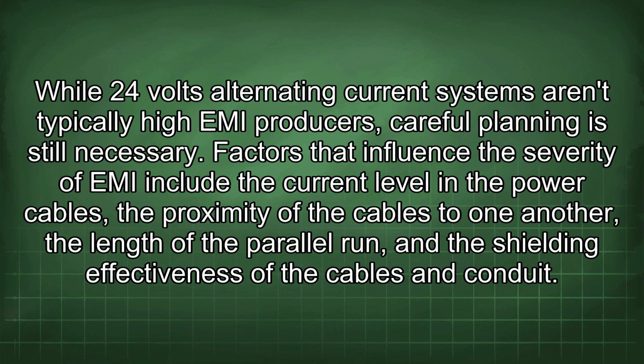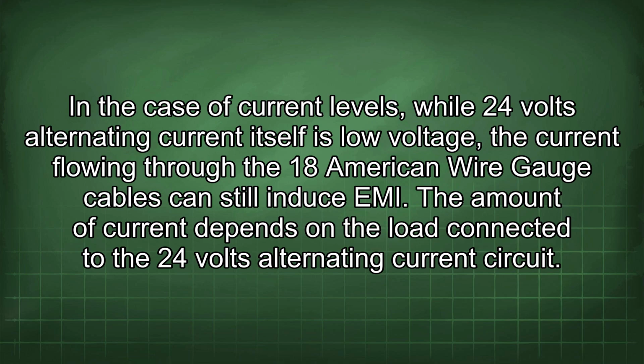Factors that influence the severity of EMI include the current level in the power cables, the proximity of the cables to one another, the length of the parallel run, and the shielding effectiveness of the cables and conduit. In the case of current levels, while 24 volts alternating current itself is low voltage, the current flowing through the 18 American wire gauge cables can still induce EMI.